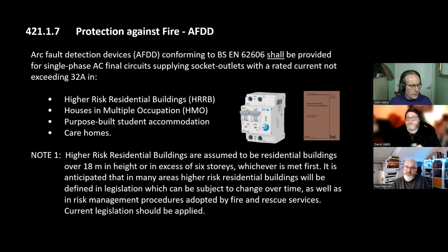If you want to reduce risk as much as reasonably practicable, okay, if you wire that care home in LSF, twin and earth or singles, you've removed that risk of fire developing on a series or parallel arc to an extent. And also you then need to look at the magnitude of energy level on that circuit. So if you've got a radial circuit that goes to, I don't know, Granny Smith's room and she's got a new telly and everything else, there's not enough load there to actually generate an arc. And if she does plug in, say, a floor heater or whatever, then the only real PVC is going to be on the flex of the cable. So these are the sorts of mindset considerations we need to be considering.